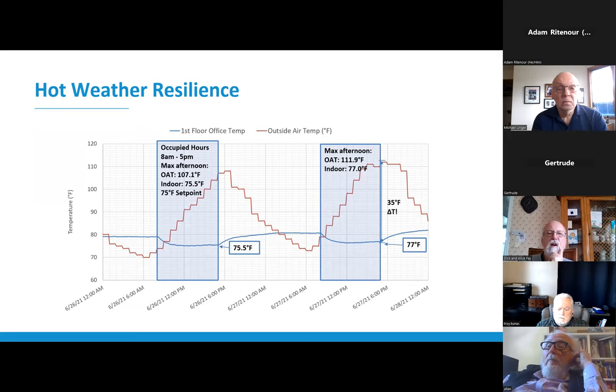So I want to highlight the hot weather resilience of this system because, like I said earlier, we did cut our cooling capacity by 41%. And lucky for us, we did get to see the hottest day on record in Portland after that retrofit. And so this figure shows some data from those two hot days. So the first day got all the way up to 107 degrees. And then the second day got all the way up to 112 degrees.